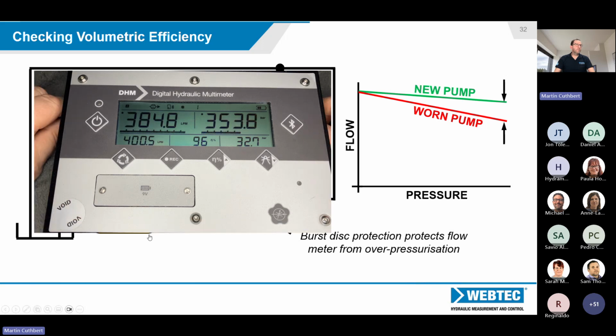At 350 bar, we can see that the flow rate has now dropped. So he's loaded the system. He's now at 353.8 bar. The flow's now dropped down to 384.8 litres. And you can see that that's automatically calculated the efficiency at 96%. So what does that mean to the user? It means that there's no complicated maths to do. It's very instantaneous. He presses one button to set the 100% situation, the reference condition, and then as he loads it, it just calculates automatically as you're going along.